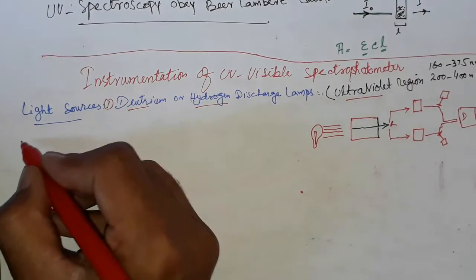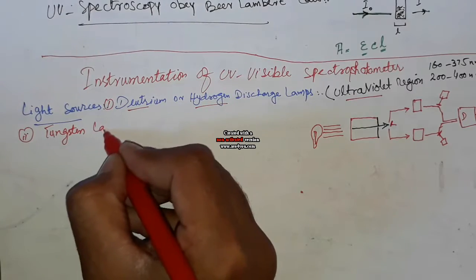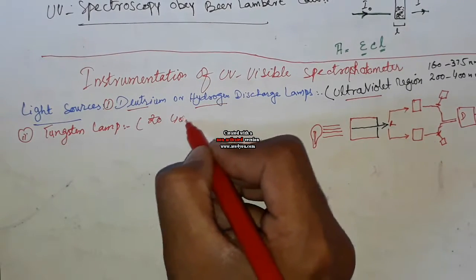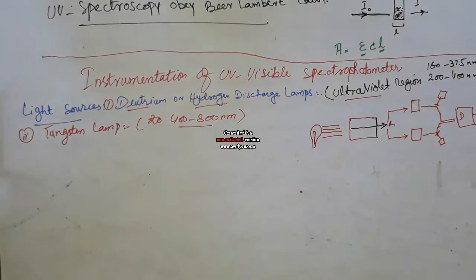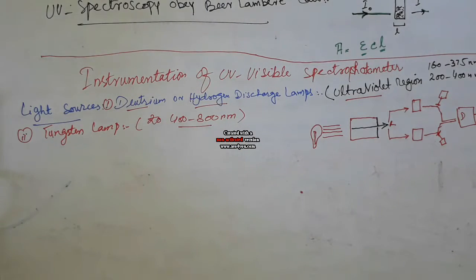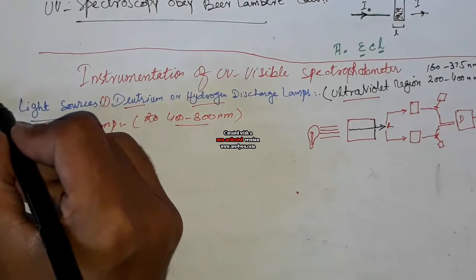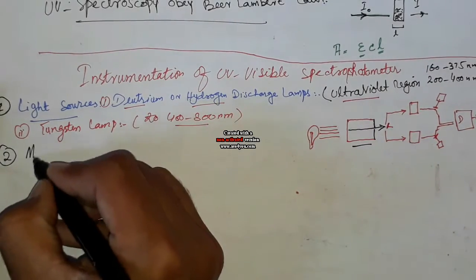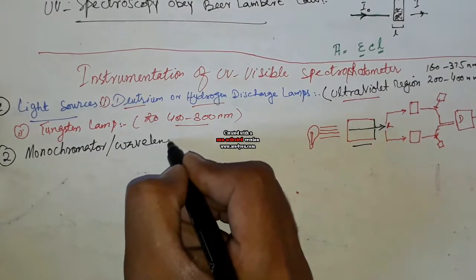These lamps have quartz windows and quartz cuvettes, which are also made of quartz and not of glass, because glass absorbs radiation in the ultraviolet region. This is the deuterium or hydrogen discharge lamp used for the ultraviolet region. The second type of lamp used in UV-Vis is the tungsten lamp, which produces radiation in the visible region from 400 to 800 nanometers. The tungsten lamp simply contains a tungsten filament.